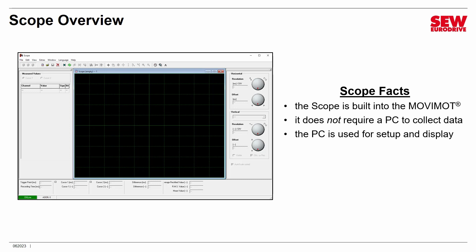The advantage of this is that the Scope doesn't require the PC to be connected to the MOVIMOT® to collect data. The Scope can collect data whether a PC is connected or not. The PC is basically just used for setting up the Scope and then later downloading the data, displaying it, and analyzing it. You can set up the Scope using your PC, disconnect and walk away, and come back at a later date to collect the data. This is really useful when you're trying to track down an elusive fault.